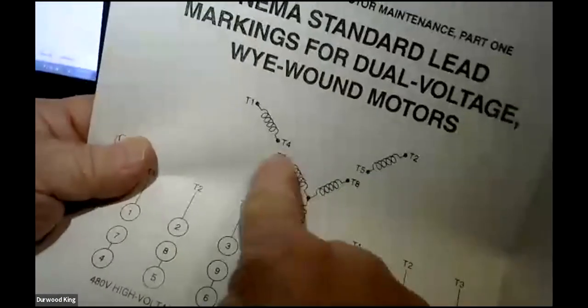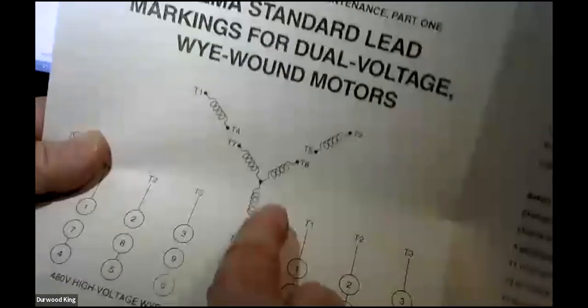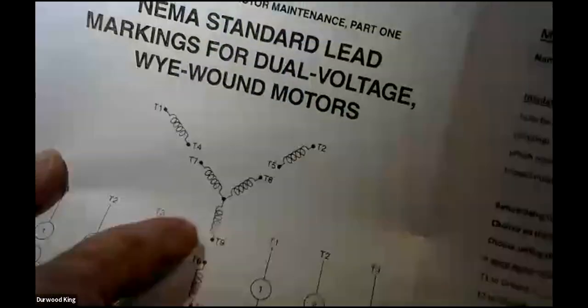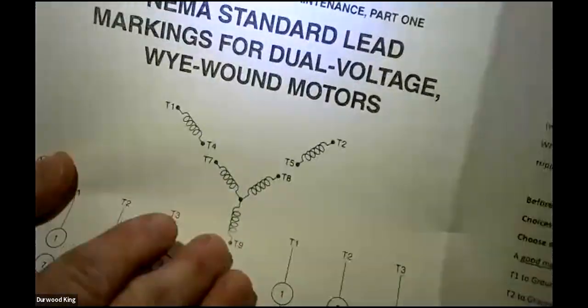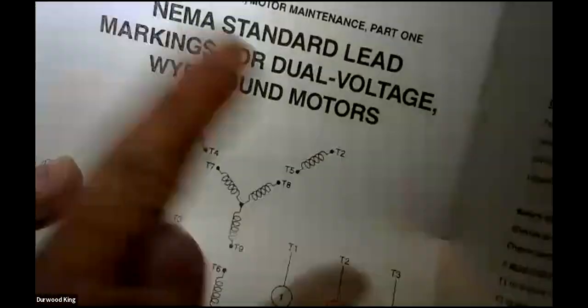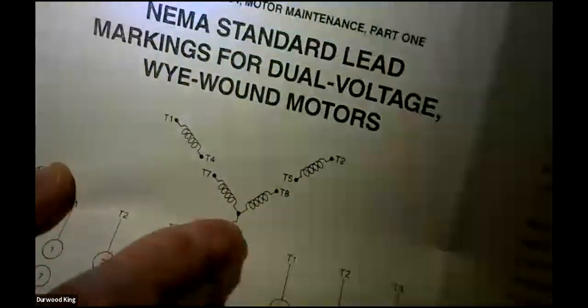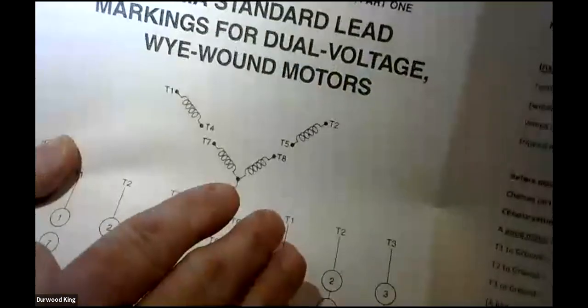You go through the meg test with high voltage from each leg to ground, and you do your continuity test through the windings to tell you if you have a broken winding. Now, let me just tell you, in the last plant I was in for 20 solid years, I saw one motor in 20 years that actually had a broken winding. And here's what happened. This is a true story.